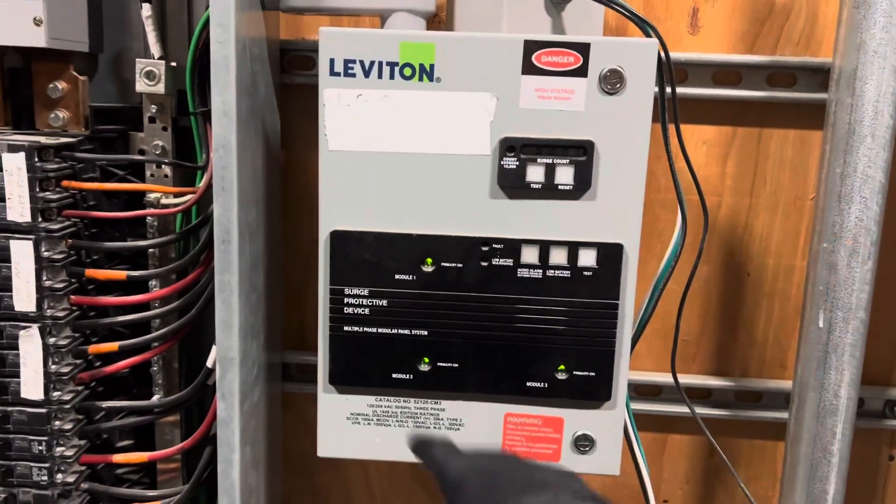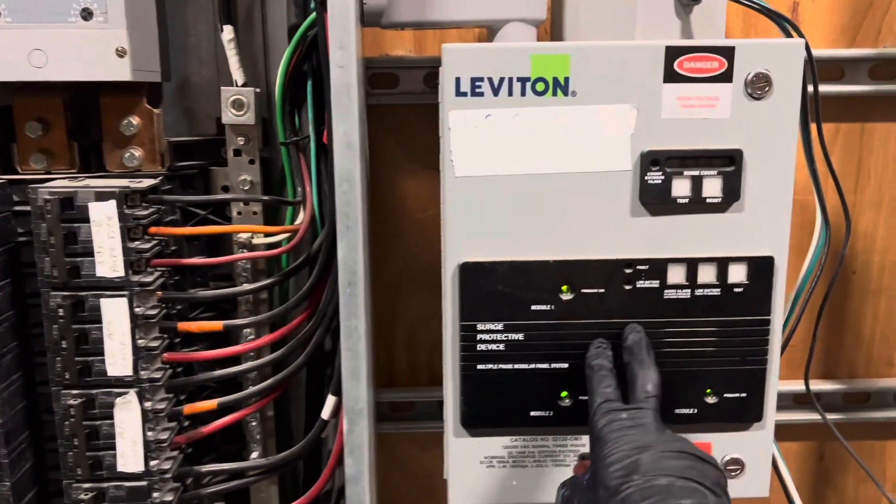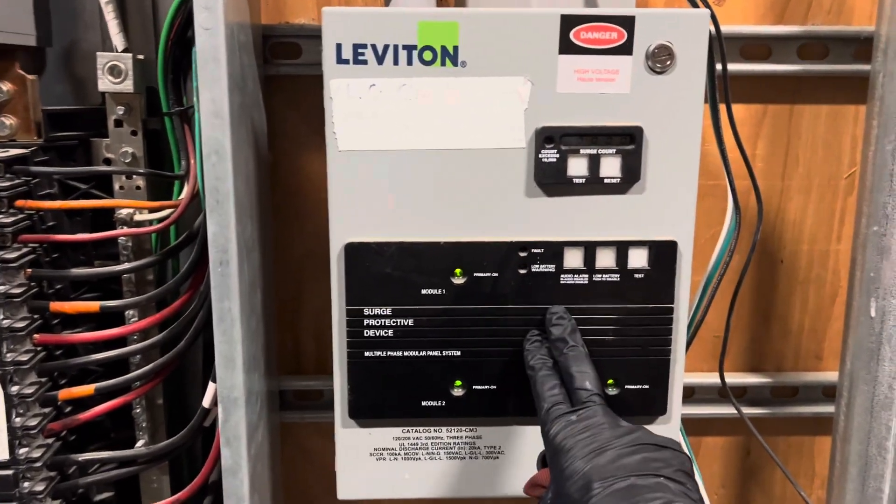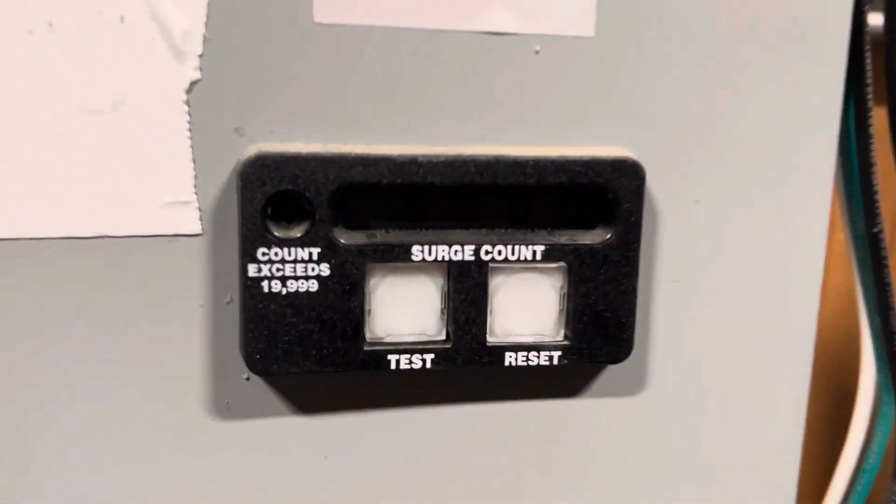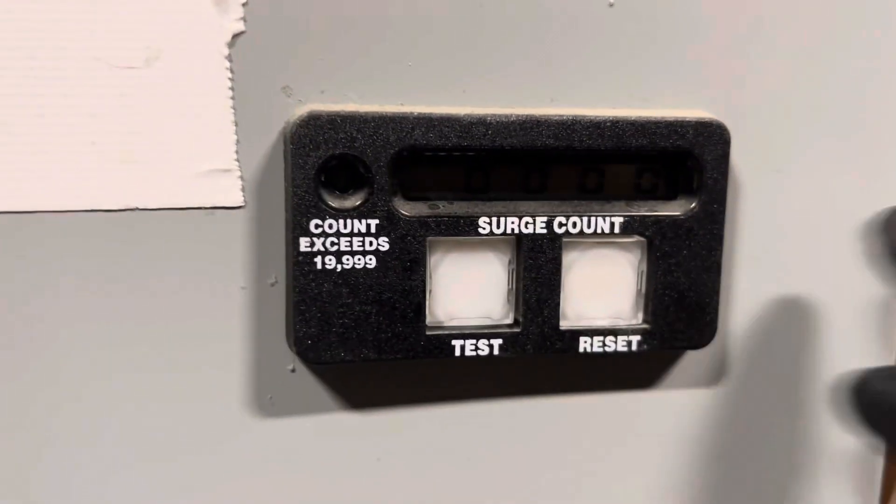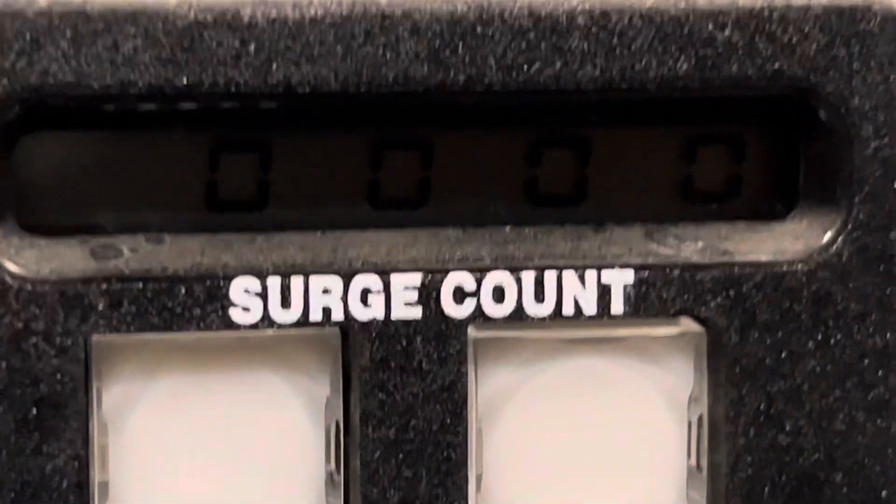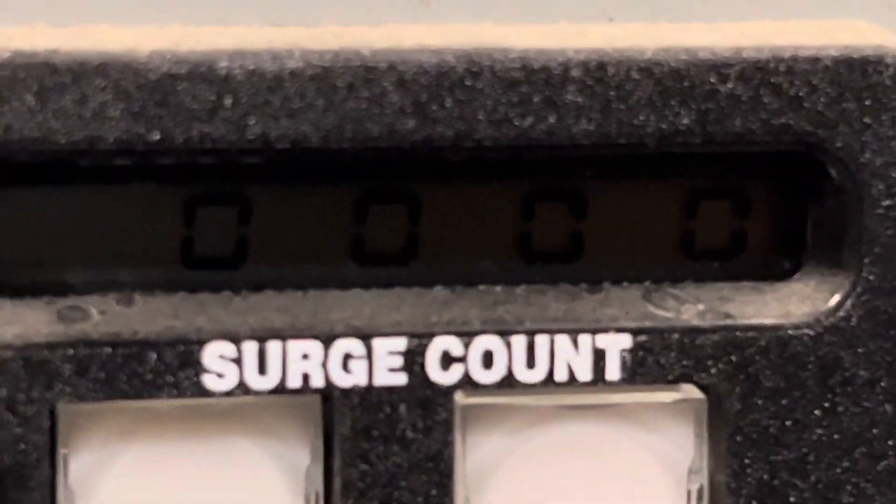You can't see it... let's see if it'll go in there. Can you see that? There you go, you can see the numbers. It counts the voltage spikes that hit the building and hit the panel that can damage your equipment. And we installed another one over here.